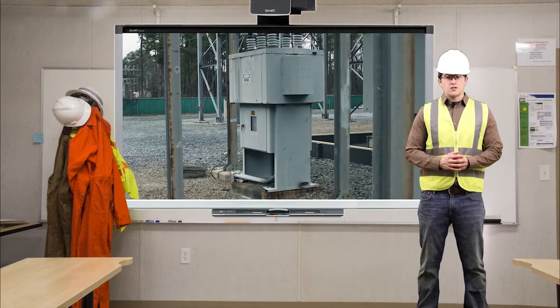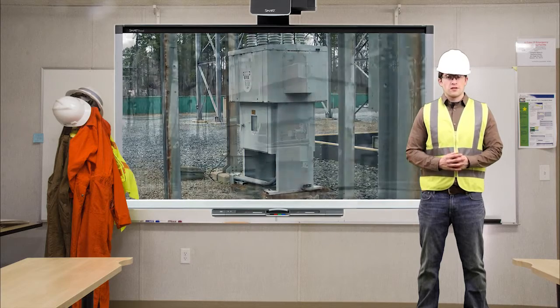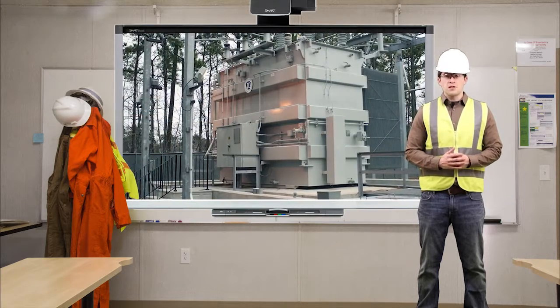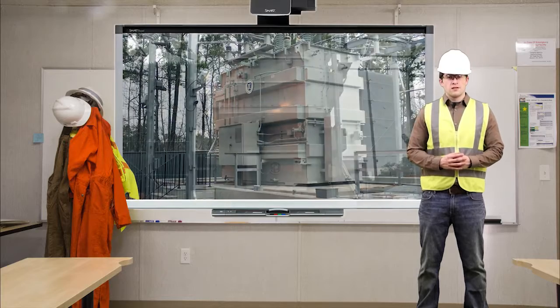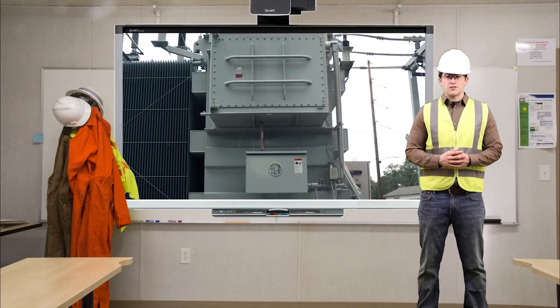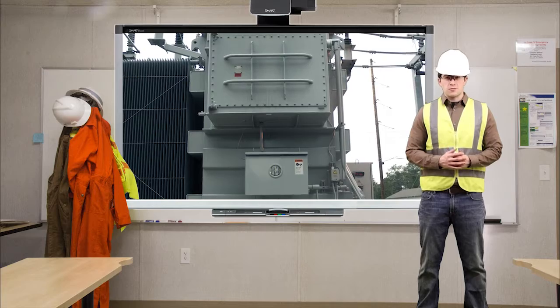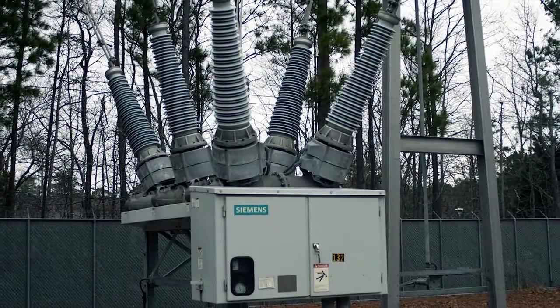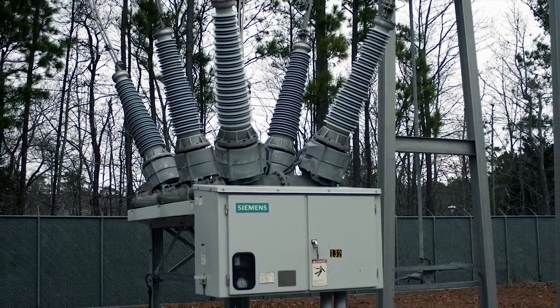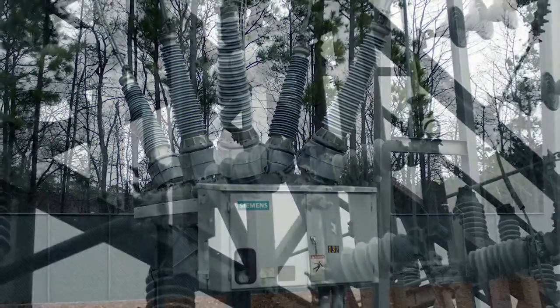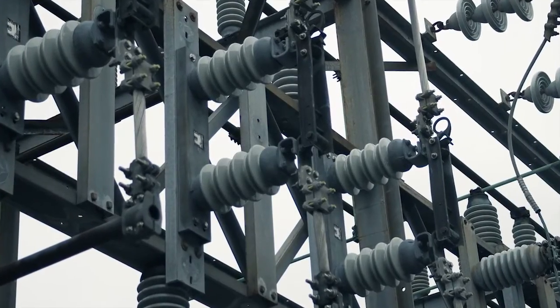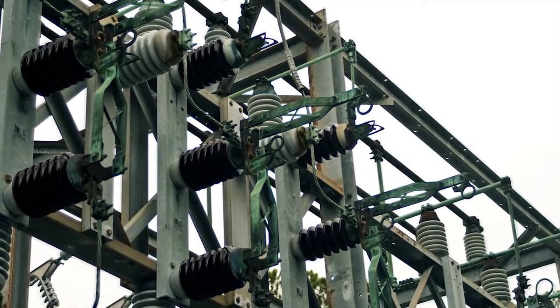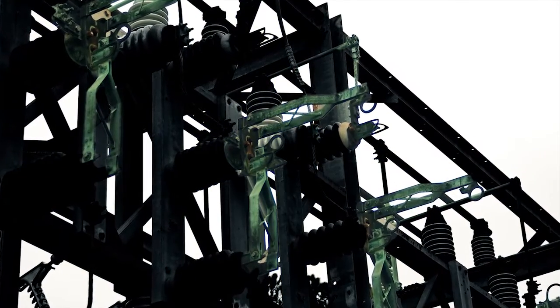Substations have voltage changing equipment such as transformers. Transformers are usually the largest piece of equipment in the substation. Some transformers have tap changers that regulate voltage for changing system loads. Circuit breakers are used for switching electric circuits in and out of the system. Switches and disconnects are used to isolate equipment for maintenance and give personnel a visual open point when performing work on equipment.